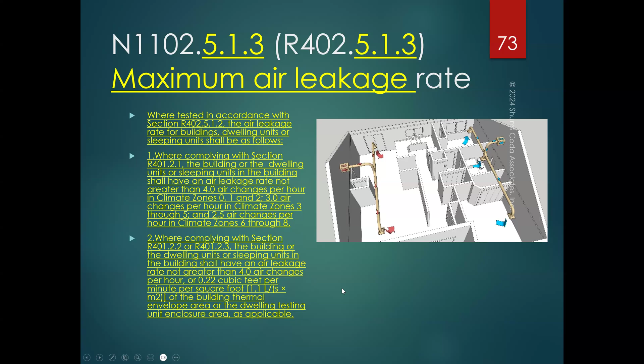Now there are a couple exceptions where in an R2 occupancy, without simultaneously testing adjacent units, you're allowed a little bit more, not permitted greater than 0.27 per square foot. The same thing, 0.27 per square foot of testing unit enclosure area. And where you have 1,500 square feet or less of conditioned floor area, the rate is permitted to be not greater than 0.27 cubic feet per minute per square foot. Oh, that's a mouthful.